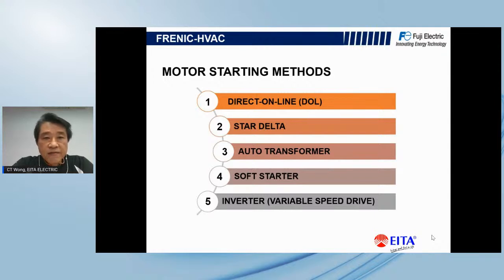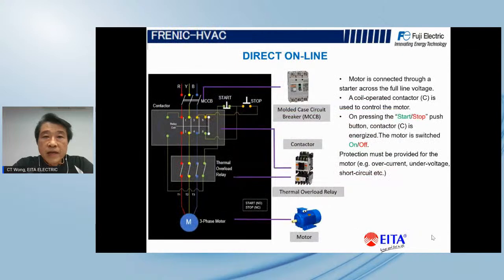Let us quickly go through the motor starting methods commonly used in the Malaysian market. You can see here, starting from direct online, star delta, auto transformers, soft starters, inverters, or what we also call variable speed drives. Okay, so let's see the slide on the direct online starters.